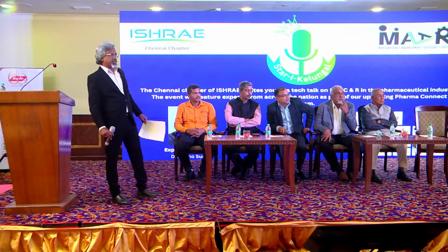I have a question to the consultant, connecting to the same question. When you design a clean room, there are three conditions that need to be taken into consideration, which is typically not given by the customer. One is the full load condition, second is the partial operating condition, and third is a no load condition.